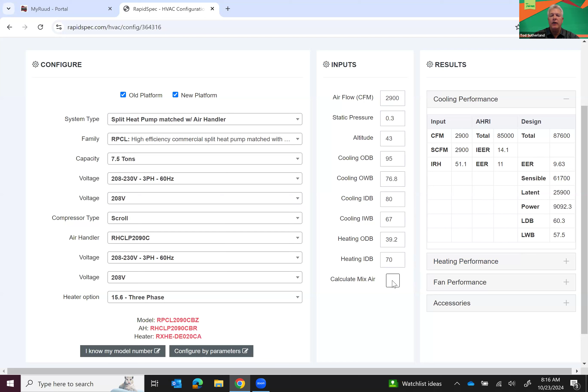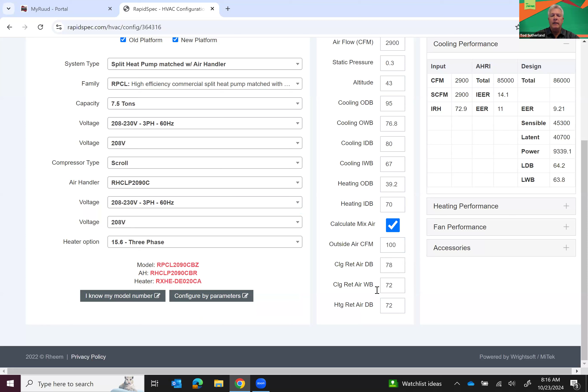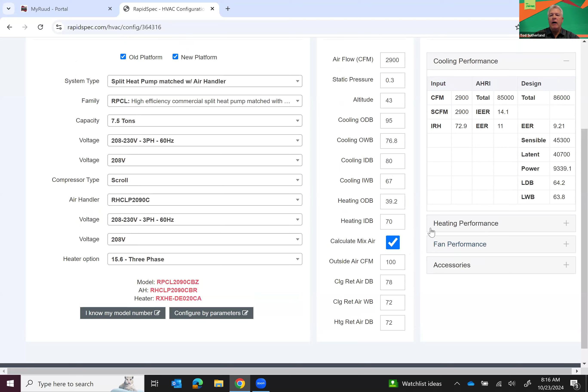Okay, now oftentimes also in commercial applications, there's going to be outside air listed on the print as well. So if you need to calculate what's going to happen in your cooling performance with outside air, you'll simply check this box and then you'll add into here what the outside air requirements are on the print. So let's say they're requiring 100 CFM. This information is typically on the print. Okay. And now we see that it's adjusted our information over here.